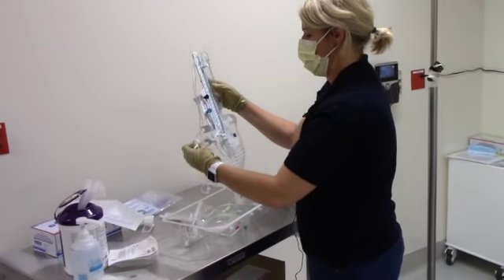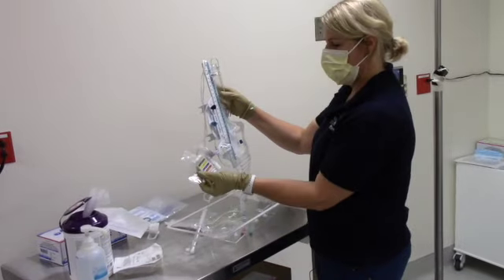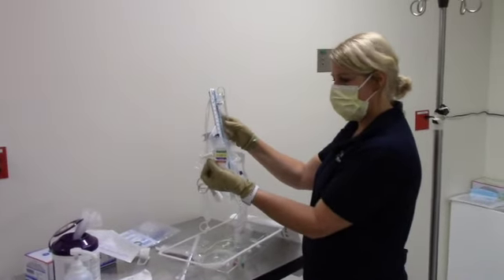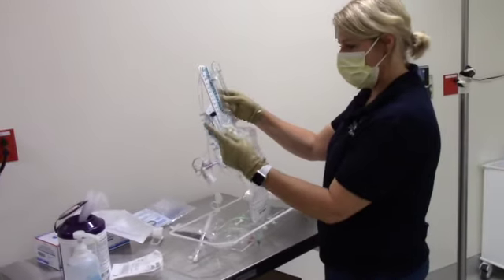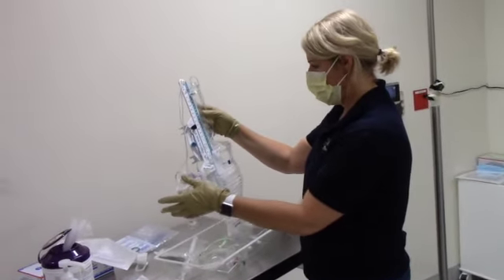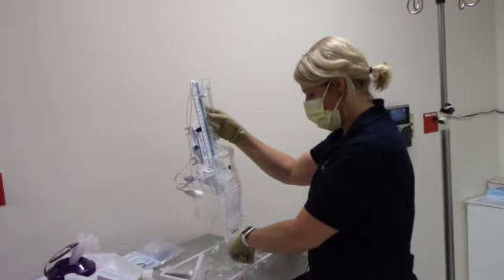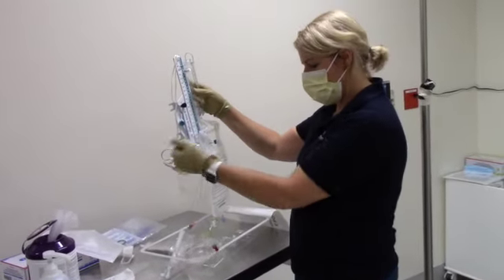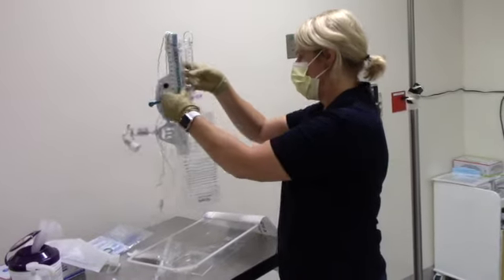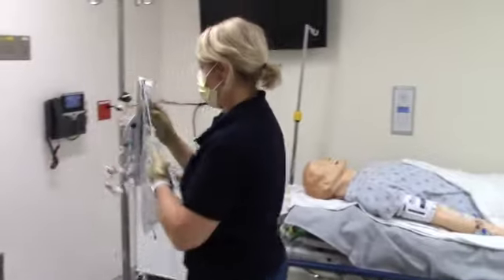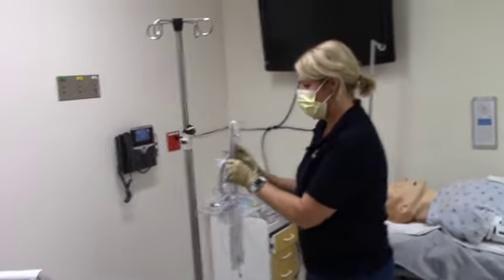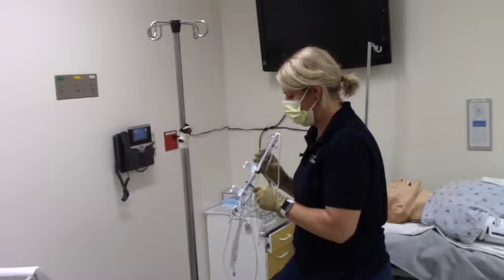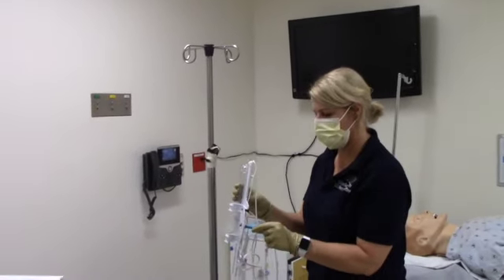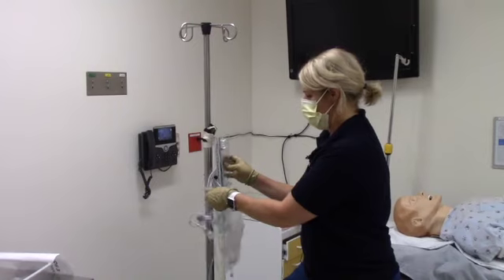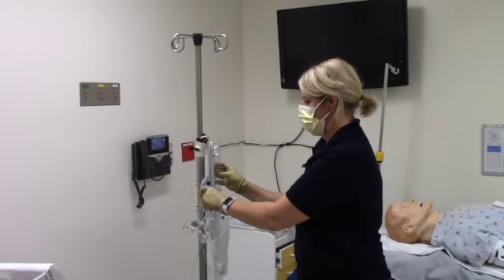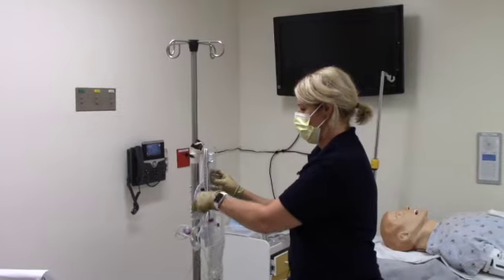Okay. And in the transducer package, there's a closed end cap that will eventually go onto the end here that we'll save for a little bit later. So at this point, we're going to attach our drain to the pole. I usually hold the tip in my hand just to keep that as sterile as possible. And then we'll very carefully, without touching the pole, attach it to the pole. There's a little blue guy here that will, there we go.